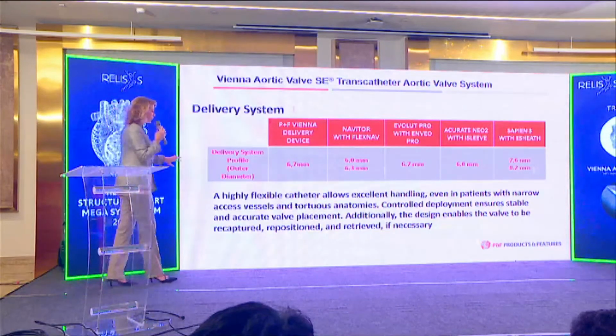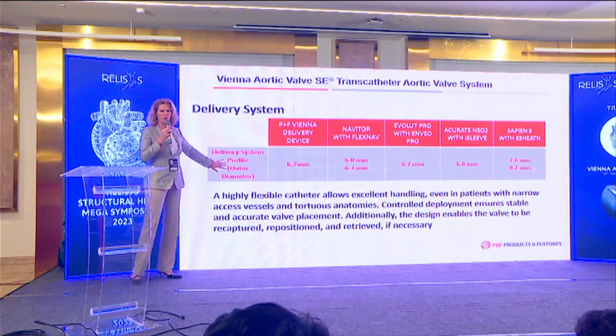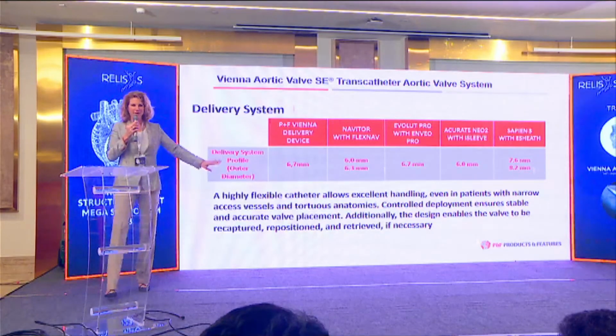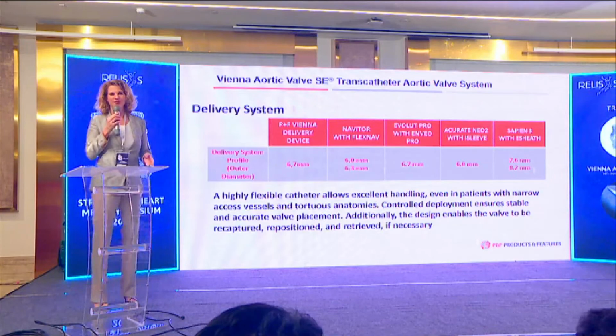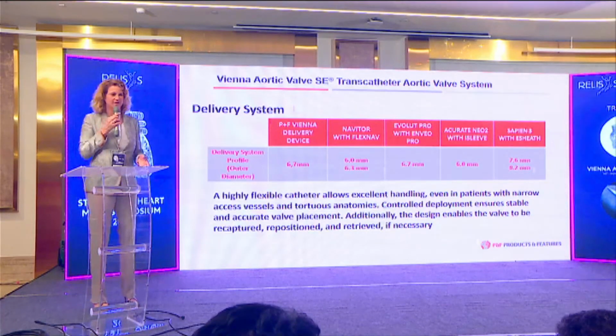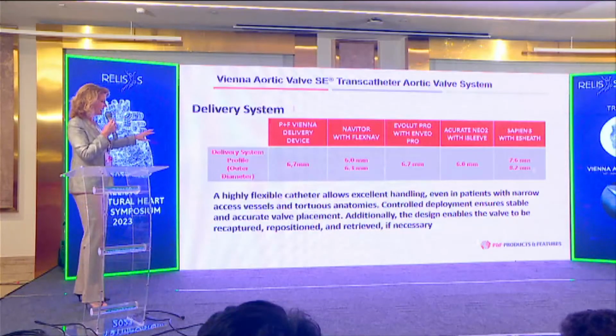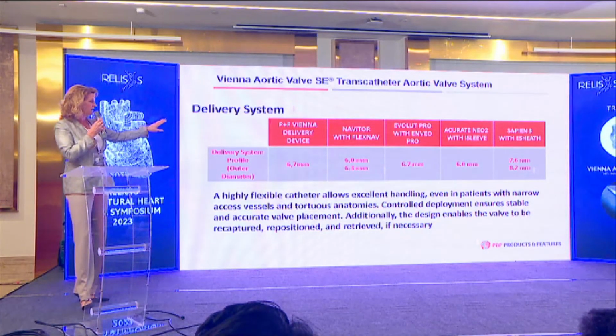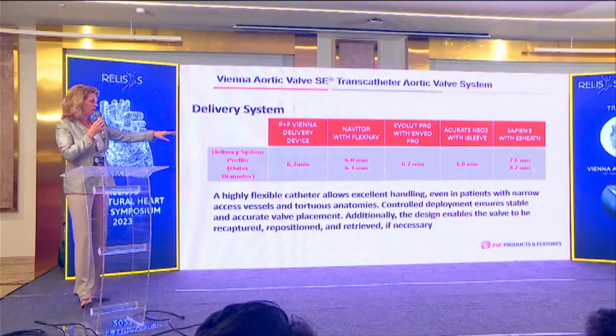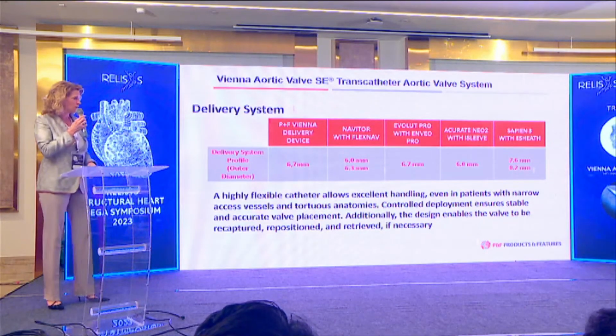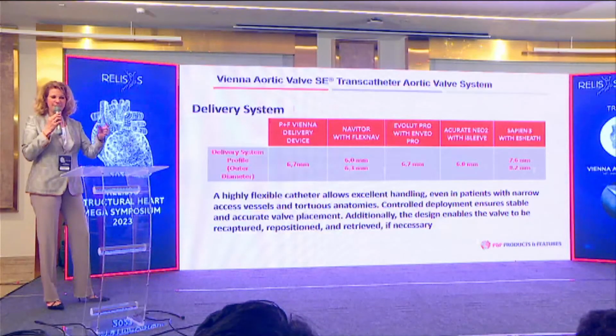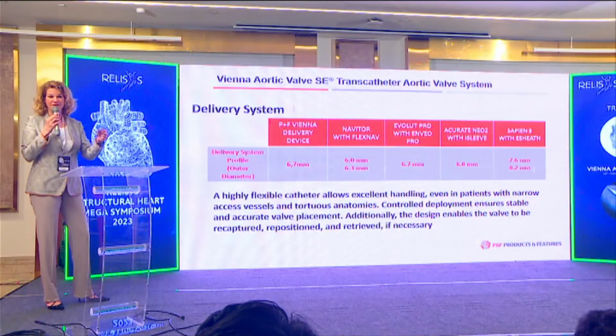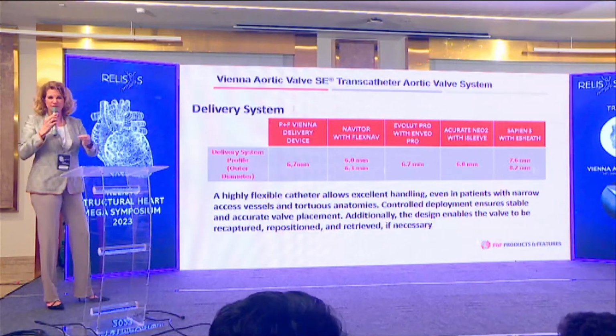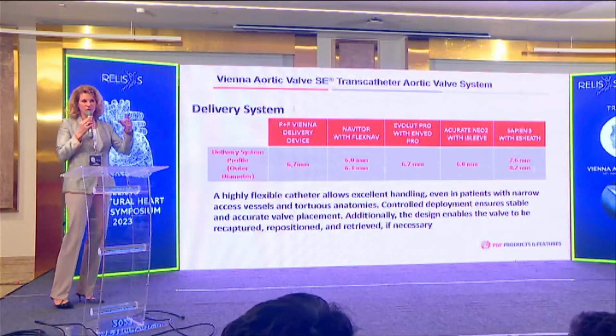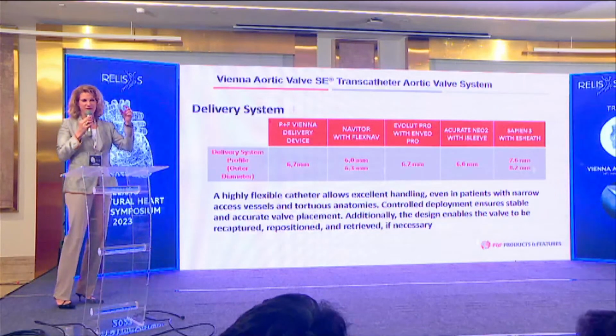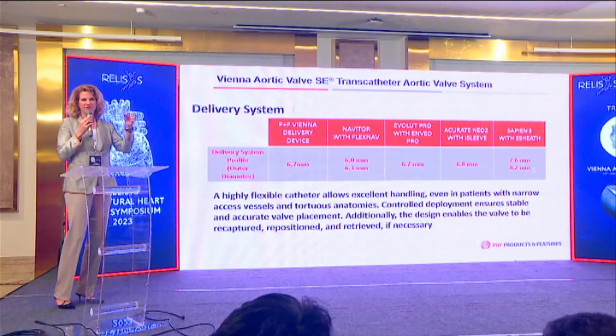This is one more important point, because I think everybody's aware that all in the industry is cheating about the French size, because everybody's measuring the inner French size, which of course will not help you if you have to cross a vessel. So these are the real French sizes measured in the outer diameter, and there you can see that the P+F, the Vienna valve, compares with the Evolut valve. Navitor is a little bit smaller from the diameter, but in the end it's the capsula of the device that will matter, because you will not be able to cross the vessel if you're only with the delivery device. You will always have to bring your valve in first, and this is why in reality it's the size of the capsule of the valve that matters.